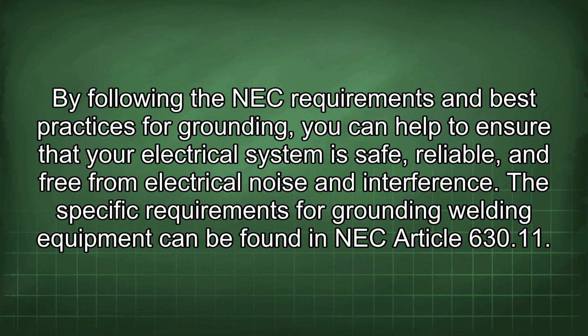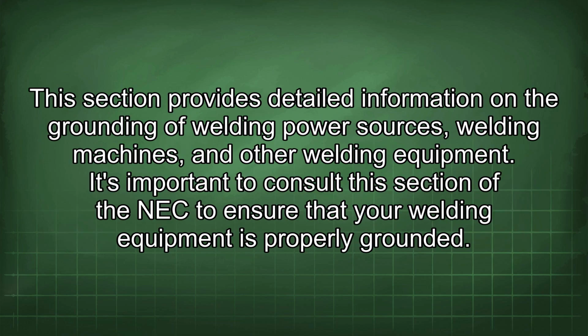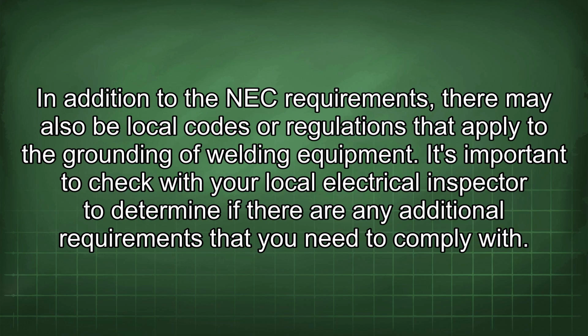The specific requirements for grounding welding equipment can be found in NEC Article 630.11. This section provides detailed information on the grounding of welding power sources, welding machines, and other welding equipment. It's important to consult this section of the NEC to ensure that your welding equipment is properly grounded. In addition to the NEC requirements, there may also be local codes or regulations that apply to the grounding of welding equipment. It's important to check with your local electrical inspector to determine if there are any additional requirements that you need to comply with.